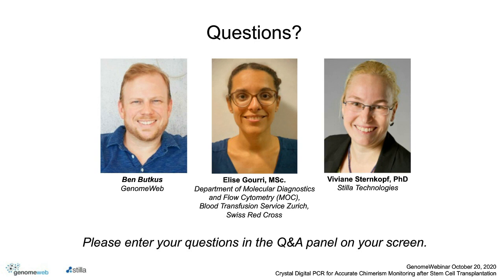The next question: is it possible to recover the PCR product after digital PCR? In the case of the Opal chip, this is not possible. However, with the Sapphire chip, we have the possibility to recover the post-PCR droplets out of the chip and analyze them with different methods afterward. There is a protocol you can use with the Sapphire chip to extract your post-PCR product out of the chip.